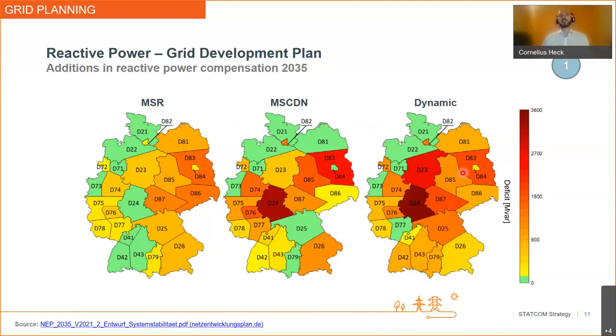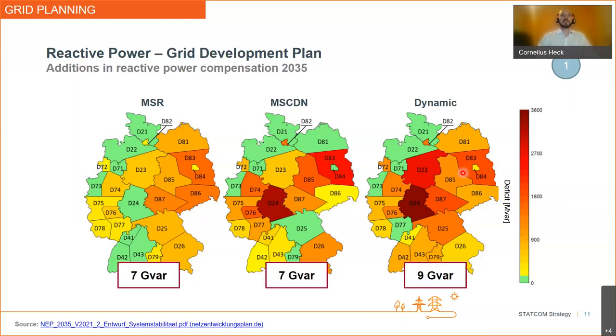And obviously the approach that I've shown doesn't work for the dynamic here. So what we do here is we subtract the N minus zero case from the N minus one case, and we have a difference in reactive power balance that we need to fill with dynamic reactive power injection. And for the year 2035, for the control area of 50 Hertz, this will lead to a deficit of 7 gigavar of shunt reactors, 7 gigavar of MSCDN, and even 9 gigavar for dynamic reactive power.